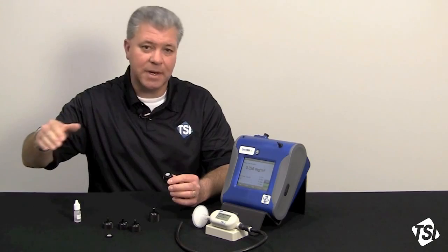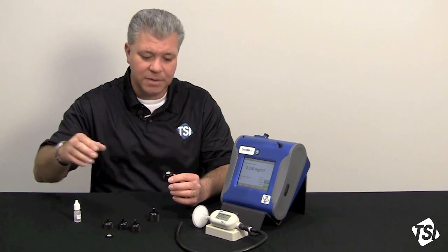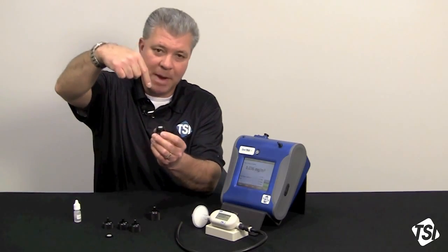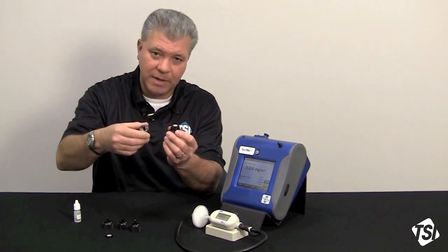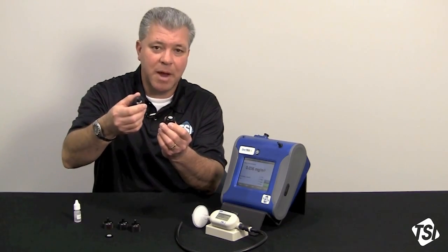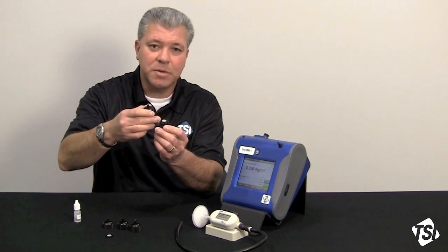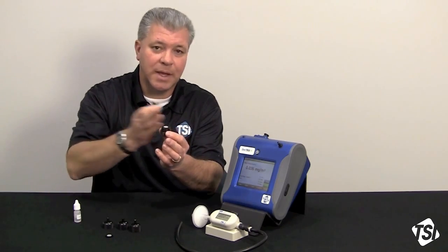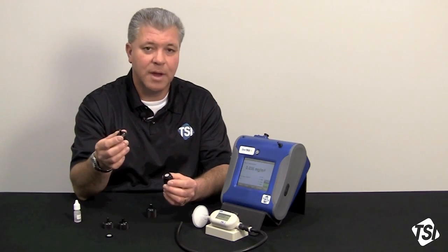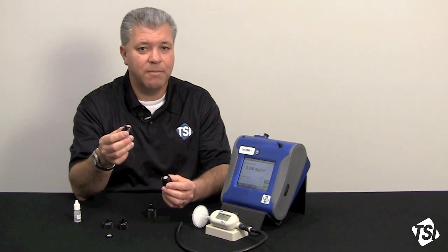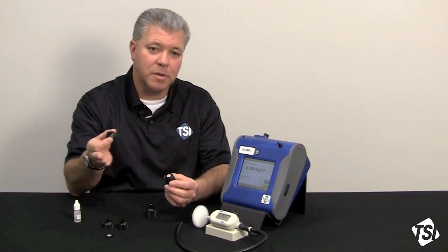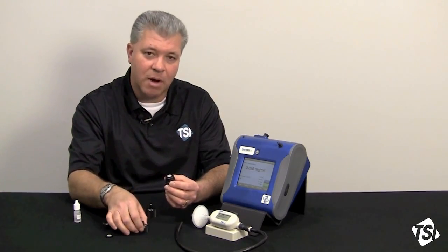So as the air velocity increases, the particle mass concentration, meaning the particles of a mass size that's associated with the cut point, and it's a D50 cut point. That means 50% of the 10 micron particles get through and 50% of them impact on the plate and everything larger. The same thing for a PM4 respirable impactor. It means that 50% of the PM4 particles, the respirable particles, get through, and 50% of the respirable particles and everything larger impacts onto the plate.